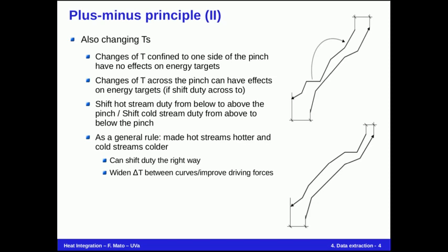As a general rule, good modifications are those that make hot streams hotter and cold streams colder, because they can shift duty the right way and also can widen temperature approach between curves and so improving driving forces, reducing the size of heat exchangers.